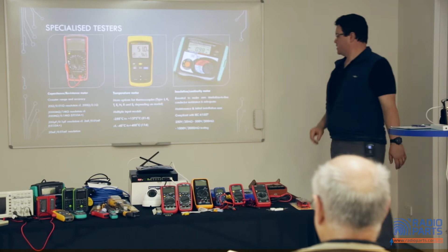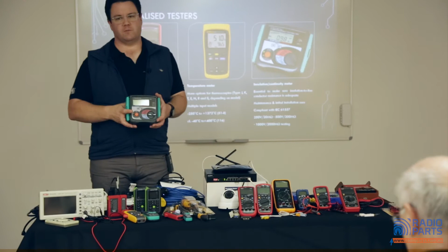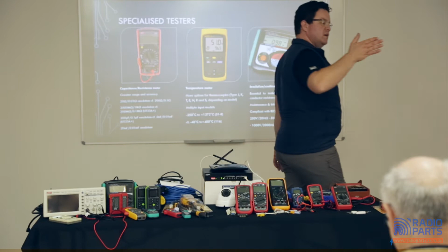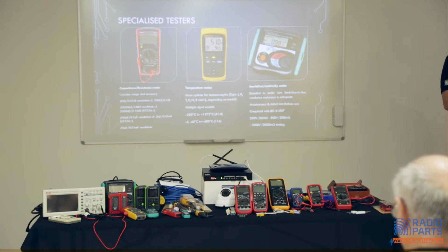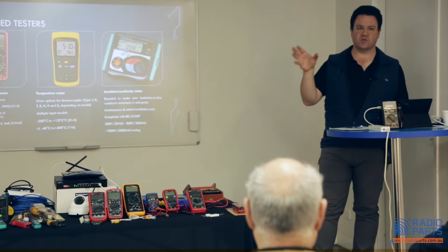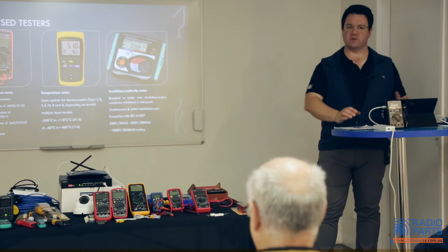The last one here is an insulation continuity tester. This is basically a resistance tester, but it's designed for electricians and industrial guys to measure the insulation rating between two things, like between the copper core and the plastic running around the outside, or from the voltage contacts on a motor to the outside shielding of that same motor. There's a whole heap of things you can do with these. They're part of an electrician's stock in trade, they have to use it. If you're worried about performance on cables over time or degradation, an insulation tester is your beast.